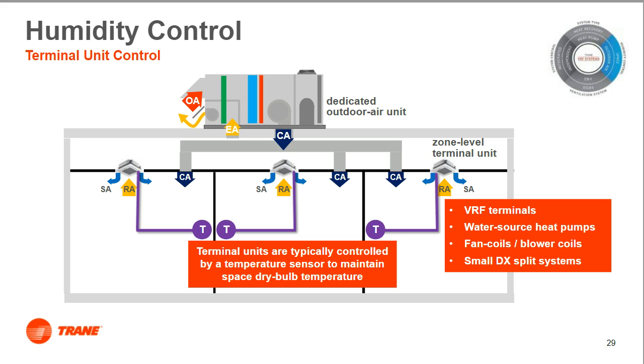Also, when selecting your VRF terminal units, make sure that they are properly sized based on the appropriate ASHRAE conditions. This is important in order to get the capacity that you need, based on the terminal unit's nominal tonnage. Designing at a temperature much higher or lower than the equipment's rated conditions may result in the de-rate of the equipment's published cooling or heating capacity. Let's take a look at what that means.